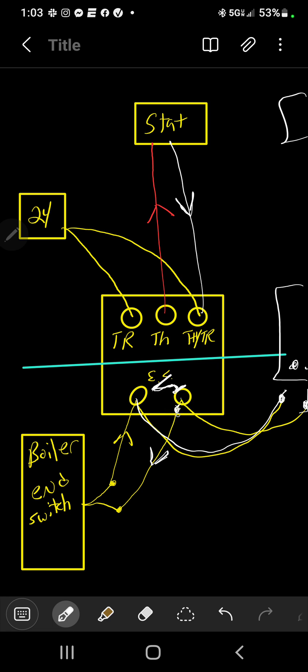So if this wire here is unhooked or any of the zone valves are unhooked, you will not get a call back just because that one middle zone valve is calling. If it's not wired in series with the rest of the zone valves, whether it's two, three, four you have, it won't kick on. Because it's going through this zone valve to go back to the boiler.